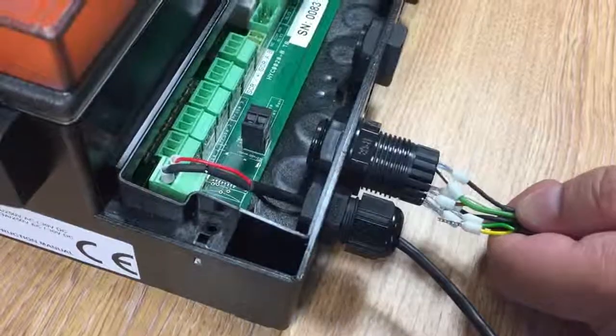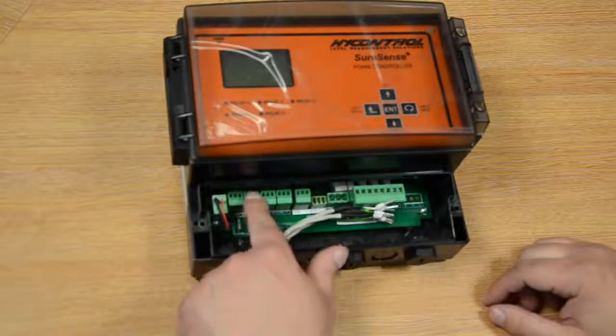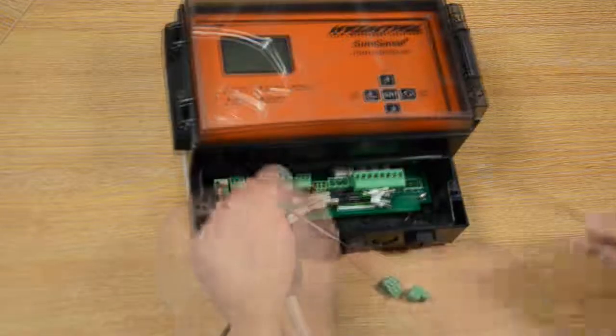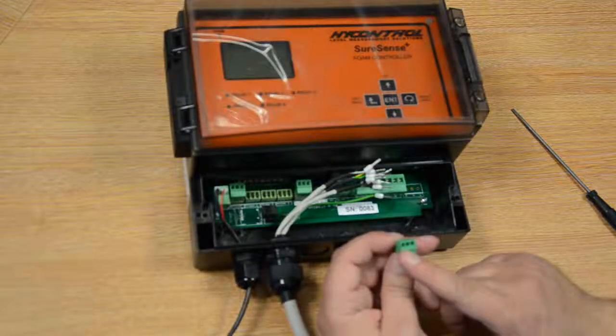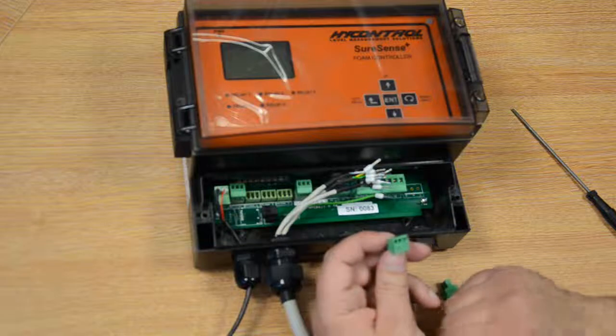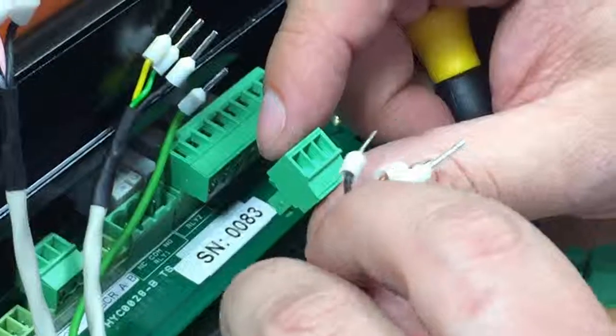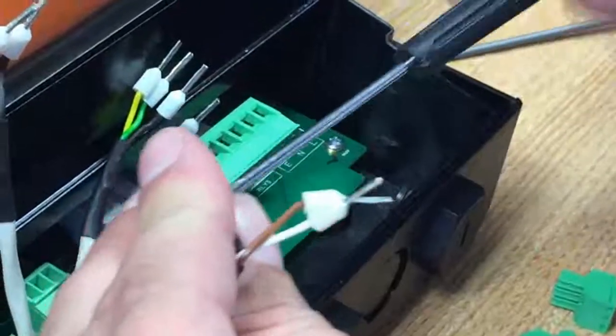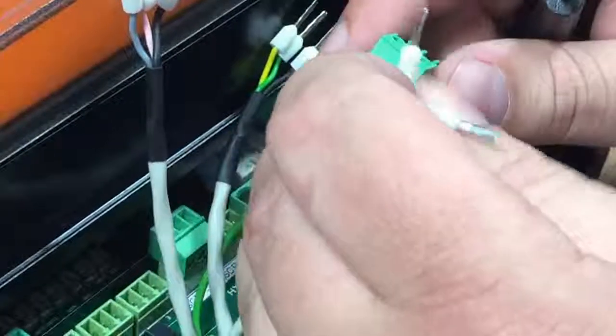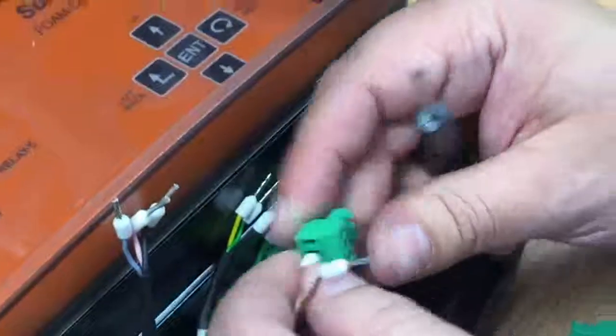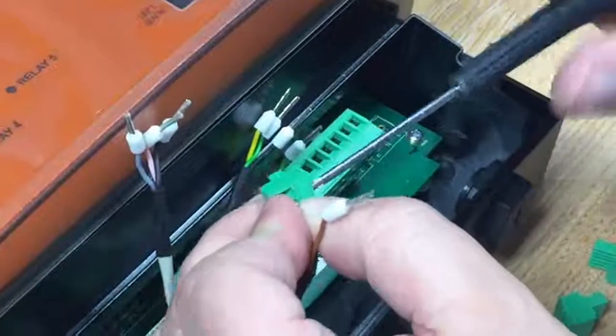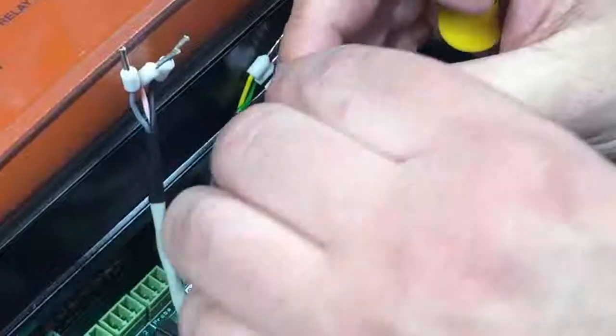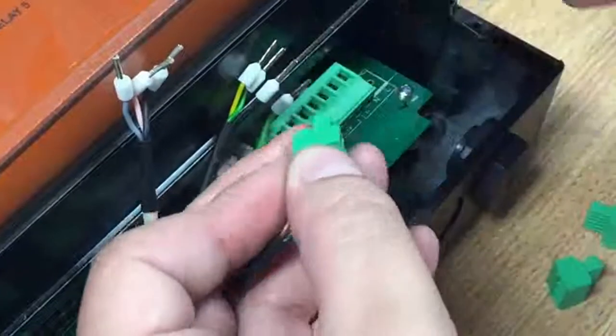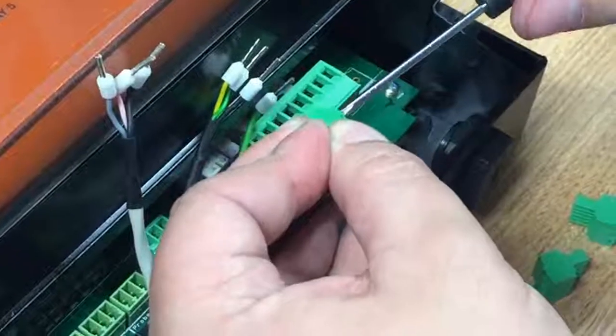Once you've got all your cables through your cable gland, we can remove the terminals, and we're going to want probes 1, 2 and 3. Once we've removed our 3 terminal blocks, the probes will always be wired with the ground on the left, the test in the middle and the sense on the outside. All of the ground wires will be black. We'll start with the brown and white cable for probe 1. Firstly, you'll put the ground into the far left terminal block and tighten this up. Next, you'll have the white cable, which is the test. And finally the brown cable, which is our sense. On a single point probe, this is all you'd need to wire up for the probe to work.